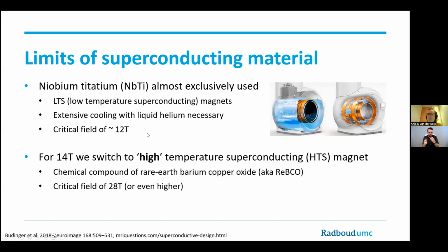So then we want to do 14T, which means we cannot use the low temperature superconductors. So what we're now doing is switching to a high temperature superconducting magnet. And I put it in brackets because high temperature doesn't mean 15 degrees Celsius, that's normal. So it still needs to be cooled, but it's cooled within a vacuum. And instead of niobium titanium, we use a chemical compound of rare earth barium copper oxide, also called REBCO. And this has a critical field of 28 Tesla or even higher, because they're already making MRI scanners with 40 Tesla, at least that's the plan.